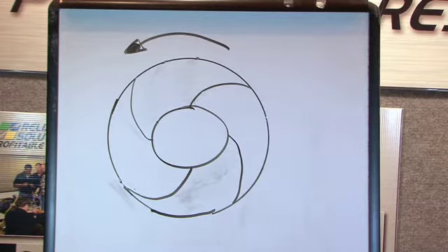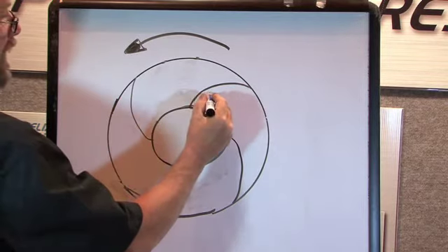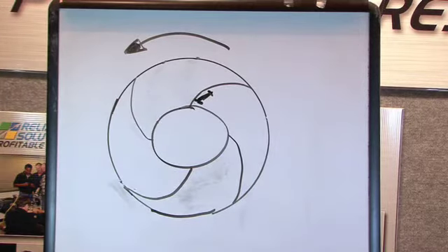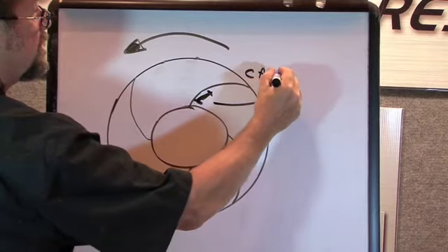By looking at where the damage occurs on the impeller vanes, we can tell a lot about what actually caused the damage. If the problem is caused by too far out on the curve or vaporization, also known as cavitation, then we'll find the damage will be located on the underside of the vanes on the leading half of the impeller, somewhere in there. That one is cavitation.